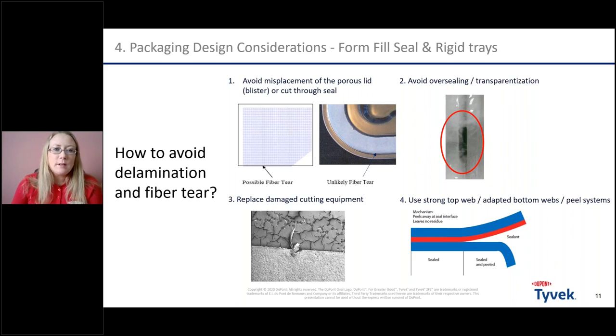Because you can seal in some filaments here and that can propagate, or you cut through the seal, that's the same issue. So the recommendation here is clearly to isolate some unsealed gap between the seal and the edge, or you can even design, like here on the picture, a flange into the tray if you have a rigid tray. So different ways of realizing that.